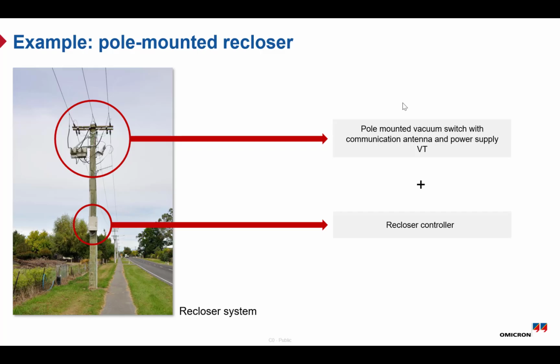All of this information, along with a control signal, is sent through a control cable down to the recloser controller. The controller itself can be mounted at different heights. Sometimes it's close to the ground for easy access, and in other cases it can be installed higher up near the recloser. This type of recloser is typically used for light and remote loads, for example in industrial areas. The main goal is to improve system reliability by clearing faults quickly and reducing outage time, restoring service automatically when possible.